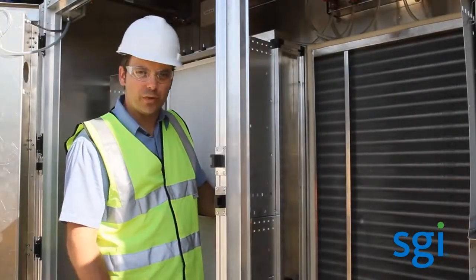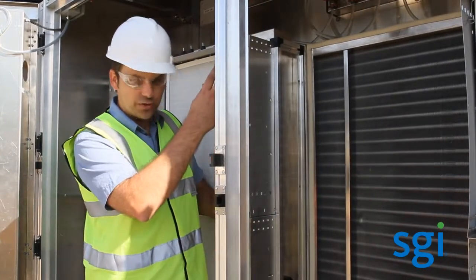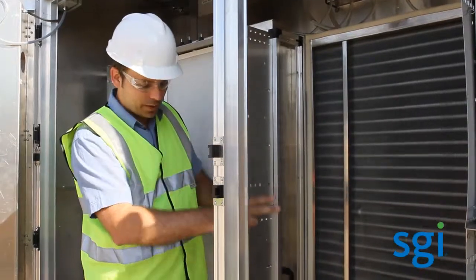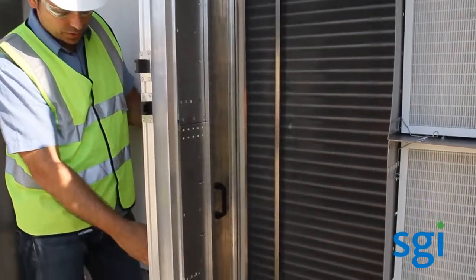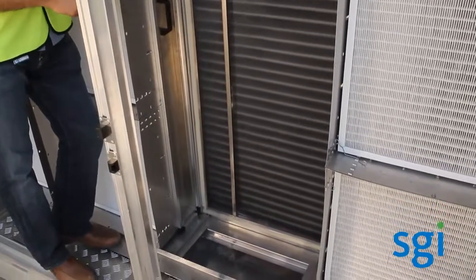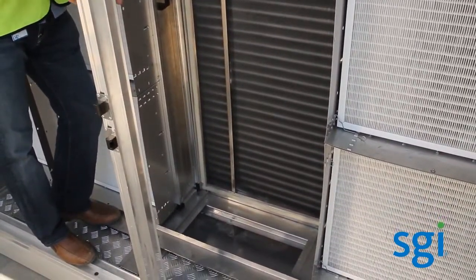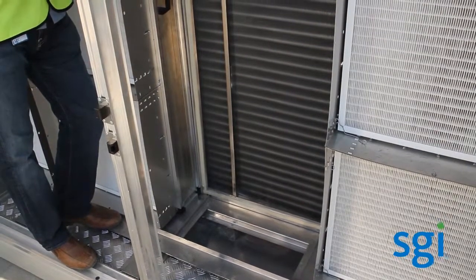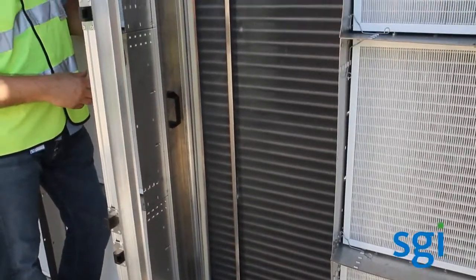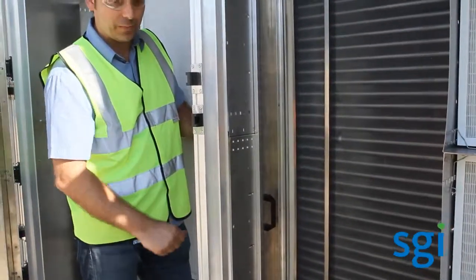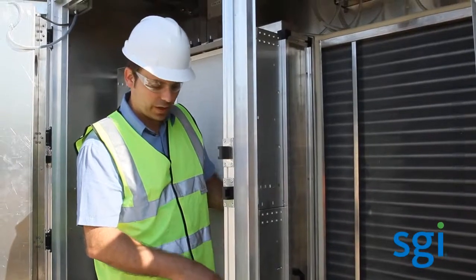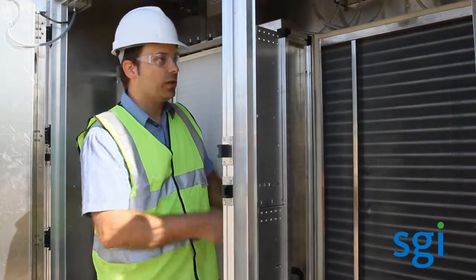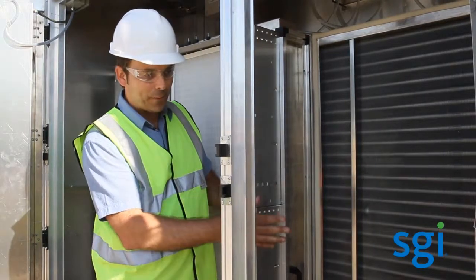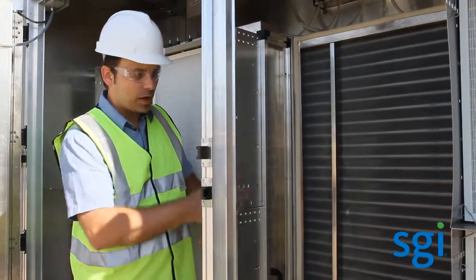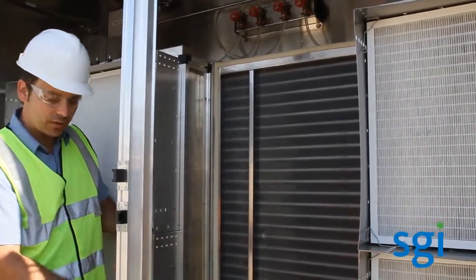So the water that flows into each one of the evaporative media sections is a single pass-through system, and it flows from top to bottom into this drain pan. And the drain pan is here just in case. When a evaporative media system is properly tuned, through all the different algorithms that we have in the monitoring control system, water should actually not even reach the drain pan. The drain pan is more for emergency, just in case. So again, the water flows from the top to the bottom, and it should evaporate. That's why we call it an evaporative media system. It should evaporate by the time it reaches the bottom. If in the case it doesn't, we have a drain pan, and we'll talk in a second about the drain.